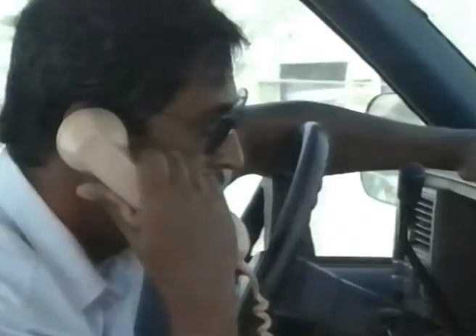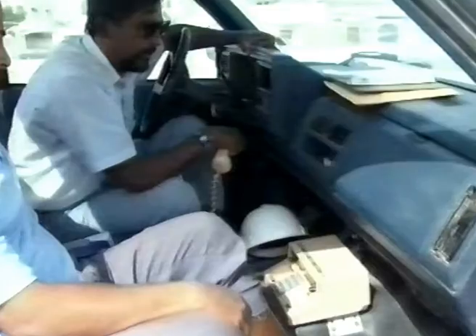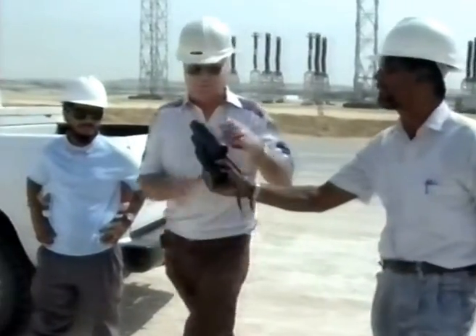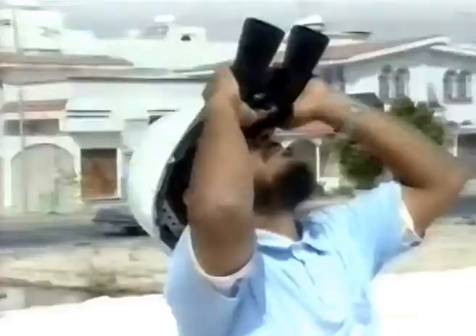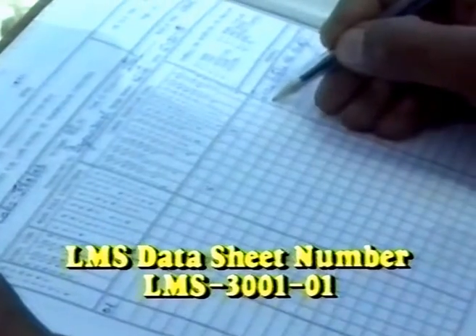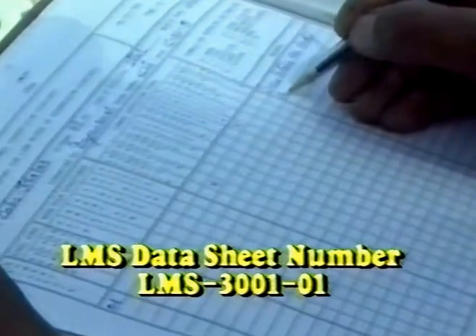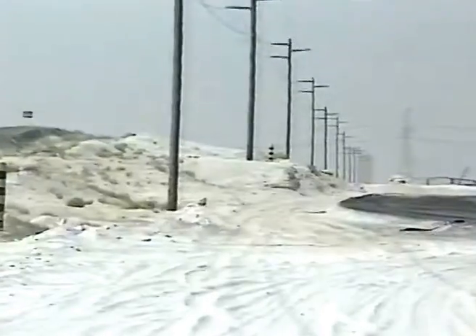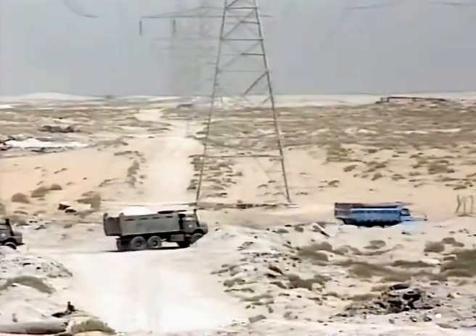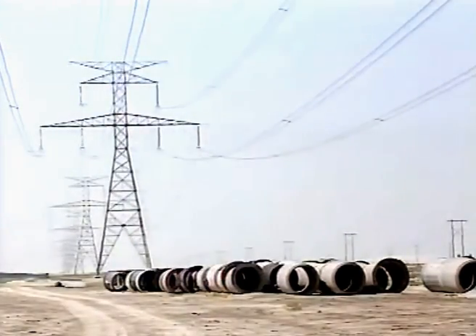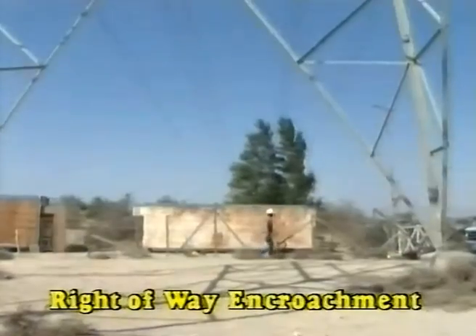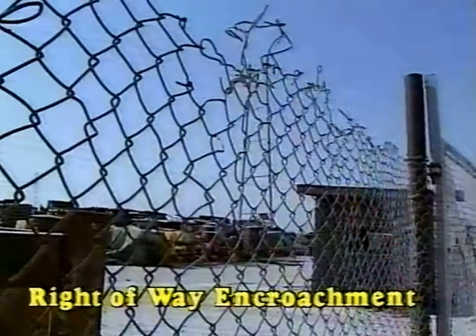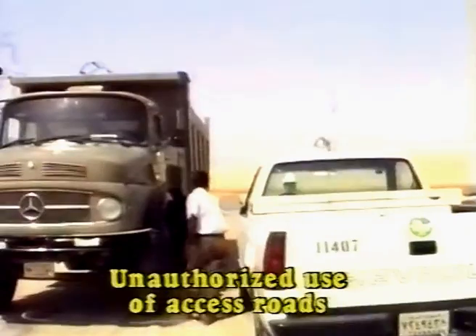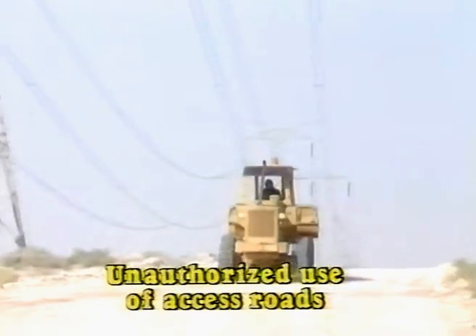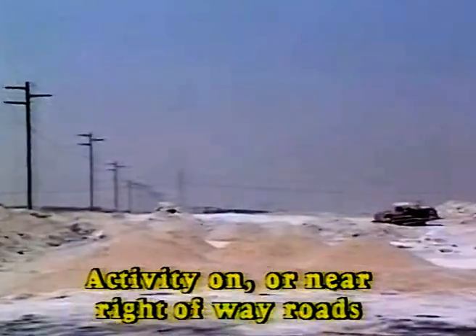The surface patrol shall inspect and report on all aspects of the transmission line, including any activity or evidence of activity that could have an influence on the security of the line. All pertinent data shall be recorded on LMS datasheet number LMS-3001-01. The following items should be inspected for all lines. Right-of-way encroachment like buildings, fenced areas, construction. Unauthorized use of access roads. Activity on or near right-of-way roads.